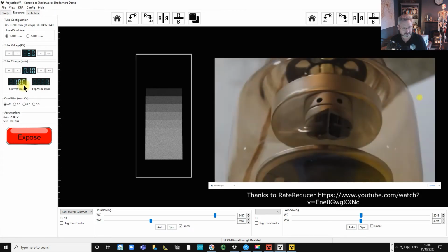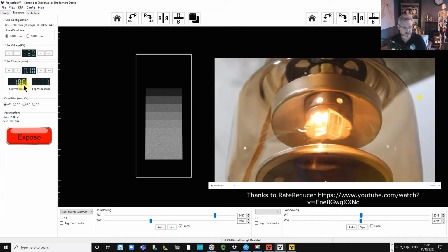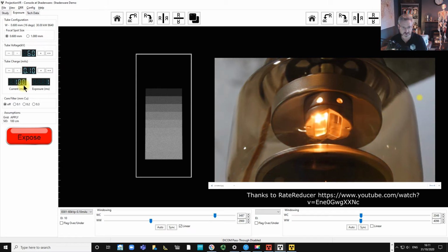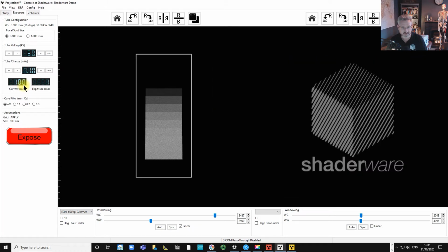When it's glowing red and yellow, then it will actually be boiling electrons off the surface, and those electrons will then be pulled by the potential difference towards the anode at very fast speeds. We're talking between a quarter and half the speed of light, depending on the voltage. The electrons will move, but until we boil the electrons off the filament, they won't go anywhere.